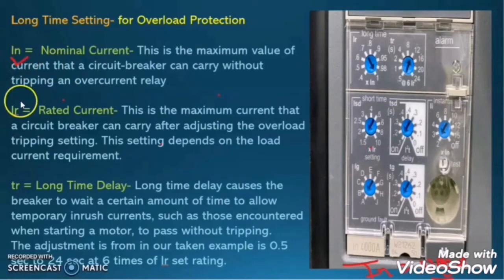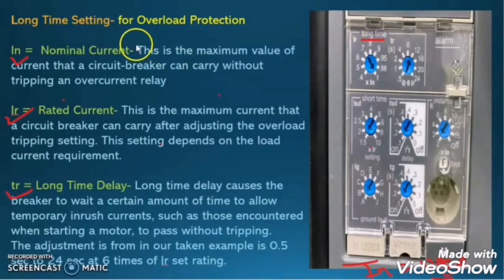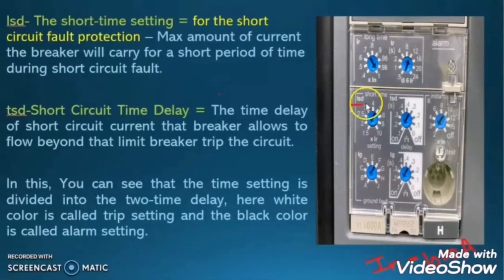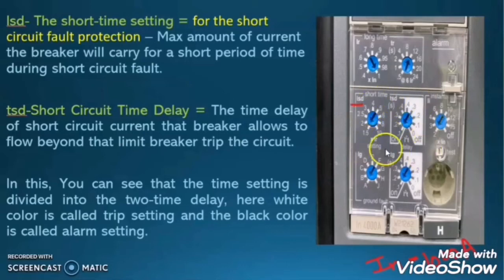I hope you now understand what is nominal current, rated current, long time delay setting, and why these settings are required in the air circuit breaker. Now let us move to the short time setting, ISD. The long time setting provides overload protection. The short time setting is for short circuit protection. Suppose there is a short circuit fault in the load connected by this air circuit breaker — there will be a huge current due to the fault. This short time setting defines how much short circuit current will be allowed and for how much time.